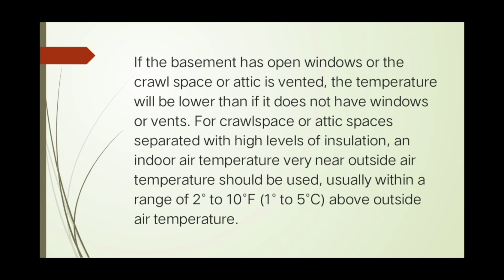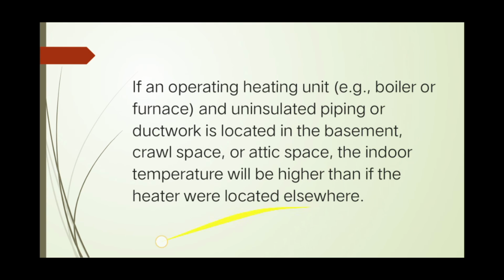Para sa crawl spaces or attic spaces, sinaseparate siya ng dalawang high levels of insulations. An indoor air temperature very near outside air temperature ay talagang pwedeng gamitin. Usually, nasa range siya ng 2 degrees hanggang 10 degrees Fahrenheit, 1 to 5 degrees Celsius above outside air temperature. And if an operating heat unit kagaya ng boiler or furnace and uninsulated piping or ductwork is located in the basement, crawl spaces or attic spaces, yung indoor temperature niya ay magiging higher kaysa kapag ang heater ay located kung saan lang. Sa maikling paliwanag, so the designer must use judgment in approximating the temperature to use in the heating load calculations for unheated attics, basements, and crawl spaces adjacent to conditioned spaces.